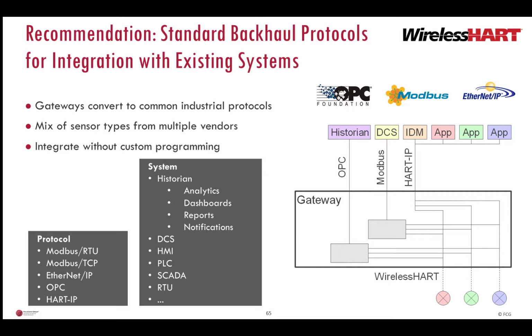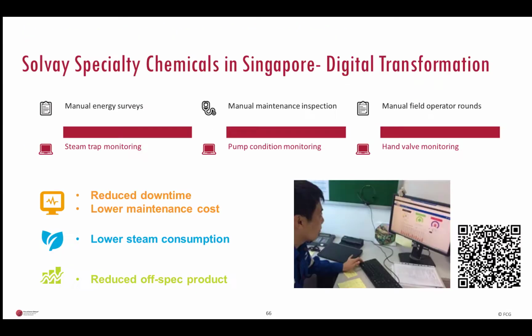This enables WirelessHART gateways to convert standard data from a mix of sensors from multiple vendors to common industrial protocols such as Modbus, Ethernet IP, and OPC for integration with existing systems. As a result, data can be brought together into applications like the plant historian or control system without custom programming or scripting. From there, it goes into analytics, dashboards, reports, notifications. Many other wireless sensor network technologies lack standard application protocol and therefore do not integrate with existing automation systems.